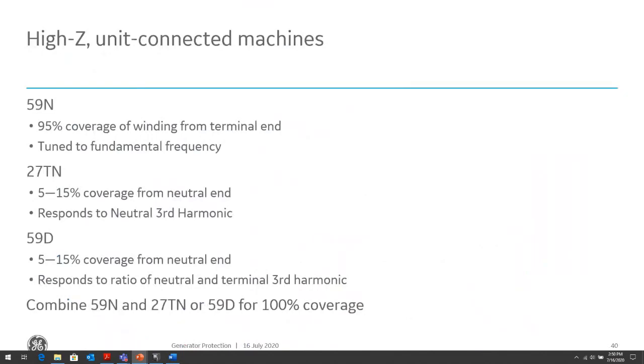Now, what do we do when we talk about high impedance grounded machines? We mentioned that ground fault currents are very low or non-existent. So if we don't have ground fault current, how can we detect ground faults? Well, what other things do we have? We have voltage. Does voltage give us an idea that there's a ground fault in the generator? It certainly does. Some of the voltage elements that will help us determine ground faults within the generator zone are the 59N, which is a zero sequence overvoltage, or neutral overvoltage, all the same. This 59N is tuned to the fundamental frequency, so it's looking at whether it's 50 Hertz or 60 Hertz, the frequency of your power system.